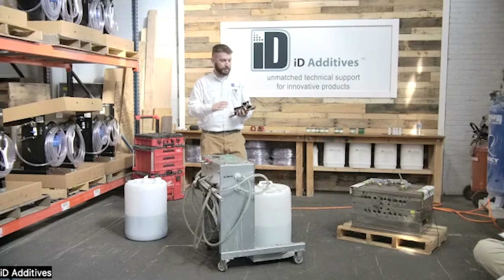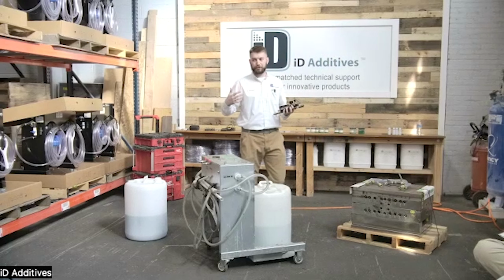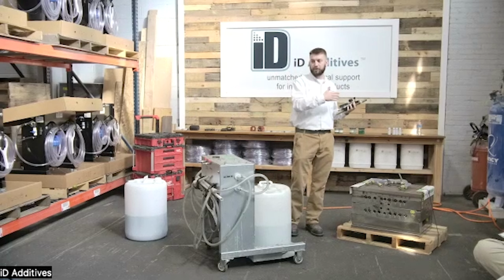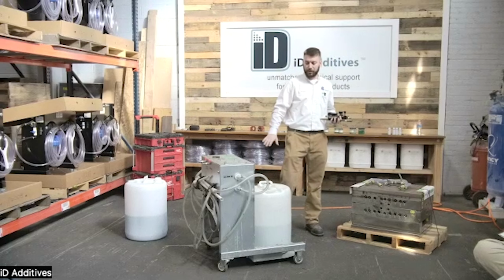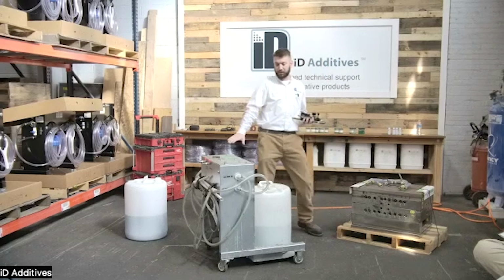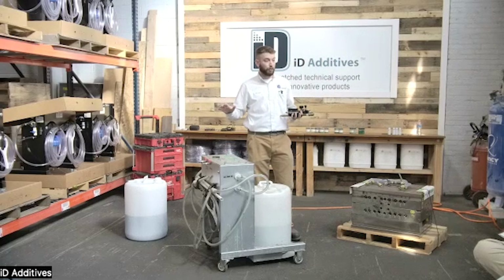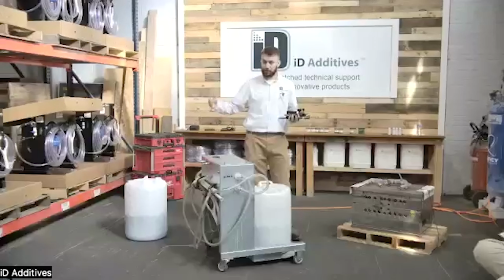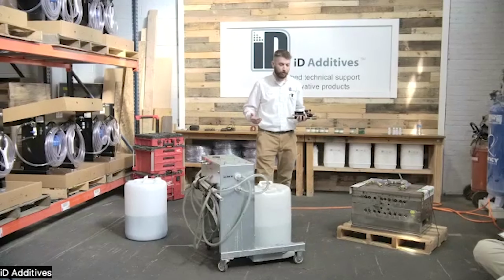But the point of having this is that when a mold comes out of production, you hook it up to your flow meter with a constant flow of water. If it's reading that high, 8 GPMs, you say okay, this time we can skip the descaling. But if it's 5.5 GPMs, you say no, we've hit 8 before, let's go ahead and hook up the descaling unit because I know I can achieve better flow.